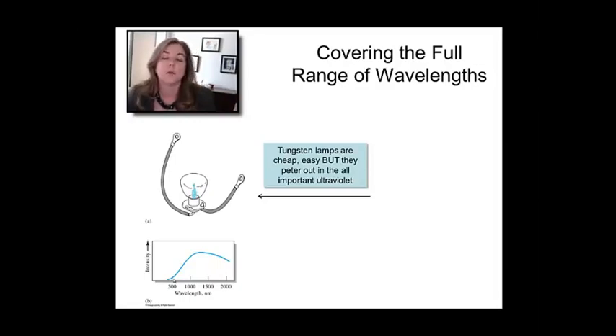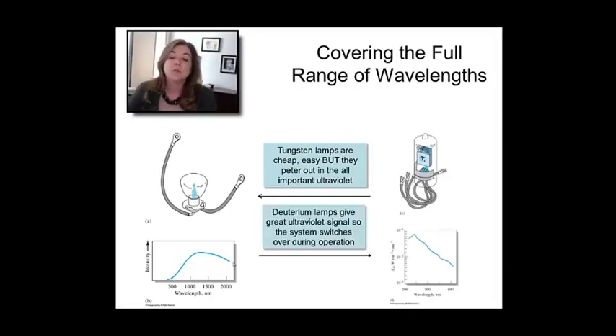So you switch to deuterium, which has the advantage of peaking in the ultraviolet but having a low visible wavelength intensity. So many UV-Vises will have a switch between deuterium and tungsten. Sometimes you'll hear it when you're scanning, clunk. And sometimes you'll see just a little bit of a glitch.